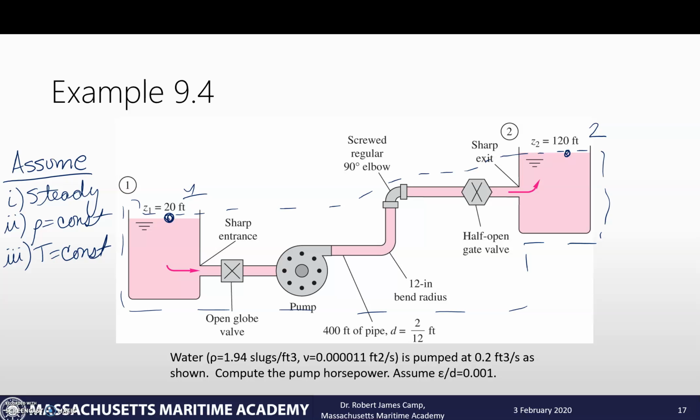To do that, I'm going to work through my normal steps. More than likely, it's going to be a turbulent flow, but I'll check that. I'll calculate out Reynolds number. If it is a laminar flow, I can determine my friction factor directly. If it's a turbulent flow, I'll go to the Moody chart. I will add up all the minor losses in the system, put that into my Darcy-Weisbach equation, and then we'll solve it. Just a couple things to note as I look at this picture.